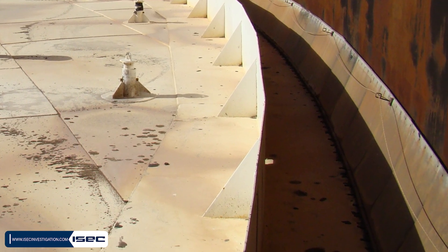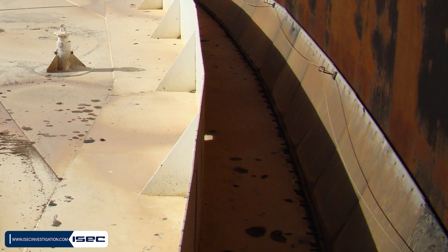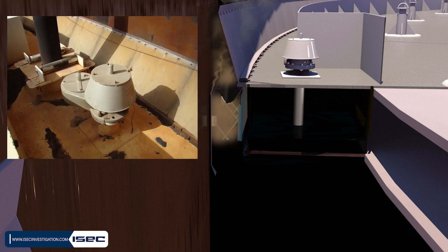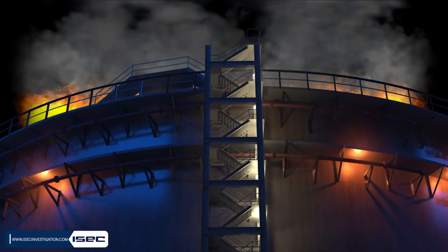Additionally, with the shunts detached and the insulating rubber attached to the weather shield destroyed by fire, the likelihood of spark generation naturally increased. Although the rim vent valve was eventually installed, unfortunately 16 months later, a second fire accident caused by lightning occurred in the same tank.